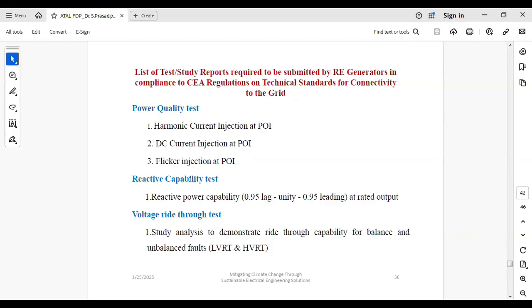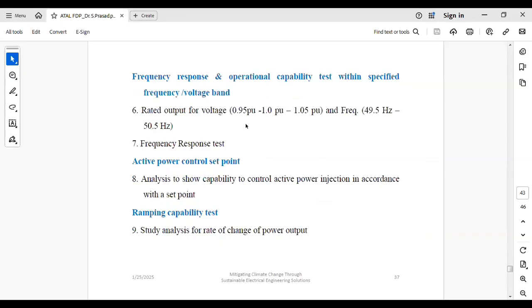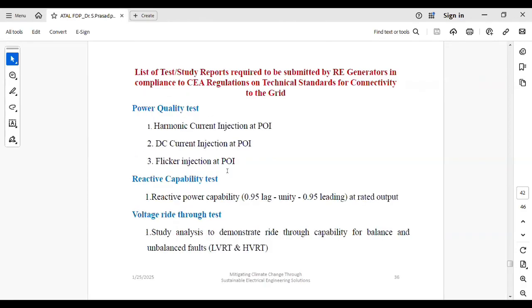These are all called the grid compliance study. Must and should, you have to get all these reports approved. Then a frequency response test, that means within 49.5 to 50.5 Hz, you have to supply the contract demand at the point of interconnection. Okay, and then active power control set point. You can control the active power at the point of interconnection. That control you must have according to the set point. You have to vary it. And the ramping capability test. That means suppose your generation goes down to a very low value, then whenever you increase it, it has to follow a percentage rate. It's not that you can change the active power injected into the network at any rate. So these tests need to be conducted and submitted for approval.